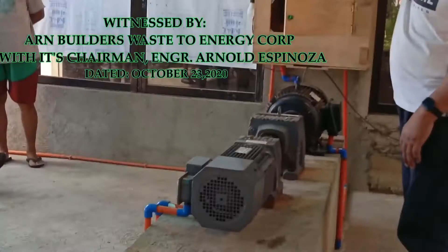So, 12 kilowatts minus 2.2, there is a surplus of 9.8 kilowatts. So the power is already there. Here there is only a ground, so the variable frequency drive is very sensitive and it will trip.